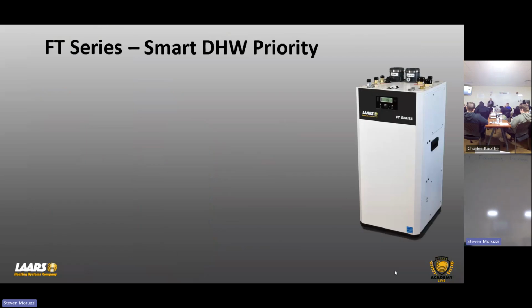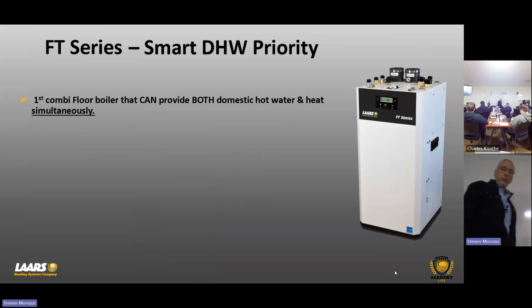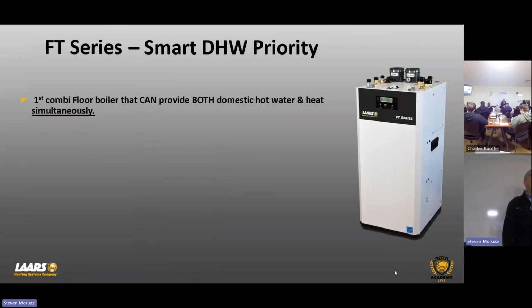Now we offer something with this called Smart Priority. It's the first combi boiler that can provide both heat and hot water simultaneously. All right, no diverter valve. And that diverter valve, I explained that at my house, I'm running a zone of heat or 2 zones of heat, and someone comes in just to wash their hands. Okay, 60 seconds. That diverter valve has to shut the boiler off. Why? Because the diverter valve has to go to domestic position, and if I didn't have flow, I'd trip limit. Now, once I'm in domestic position, I got to go back through the whole pre-purge and all of that. At 30 seconds, 60 seconds, shut off the faucet, I got to shut off the boiler again and go back up. You're going to have multiple cycles.